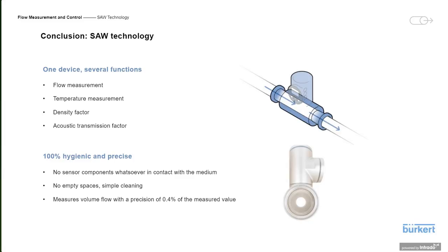The FlowWave is a 100% hygienic design, with no sensor components in contact with the medium. There's no empty space. It's simple cleaning. And the high performance you have seen in the dosing video with a precision of 0.4% of the measured value.